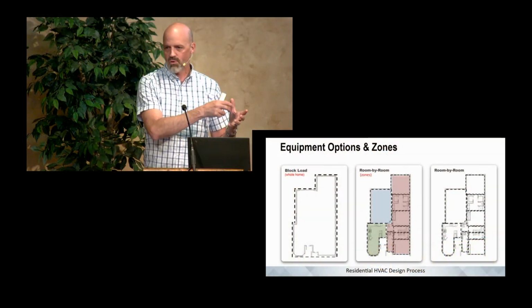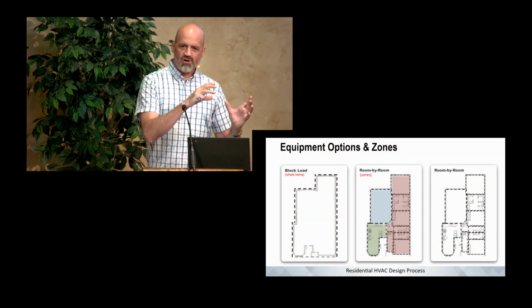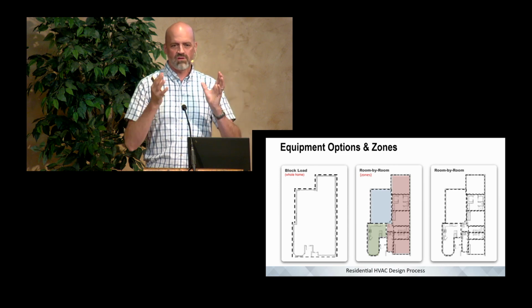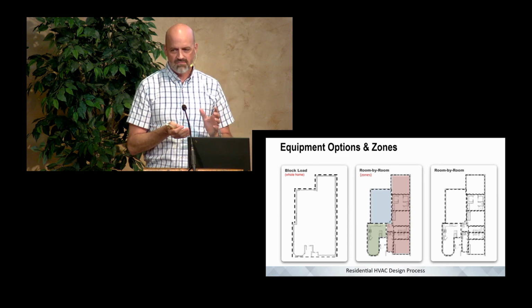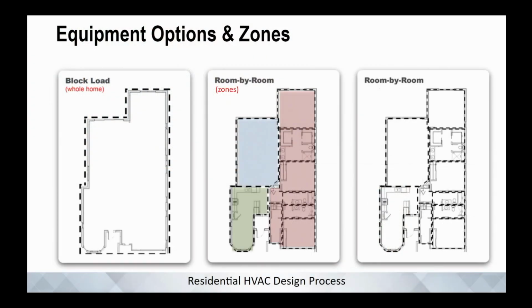So, on the left side, block load—this is how you calculate the heat load or cooling load of the home. Block load looks at the envelope overall: how much heating and cooling needs to go into or be pulled out of your house—the roof, the walls, the windows, the floors, and everything inside. The right-hand side is room load: you take the block load and chop it up into different rooms, each with different needs for comfort, heating or cooling, and airflow.